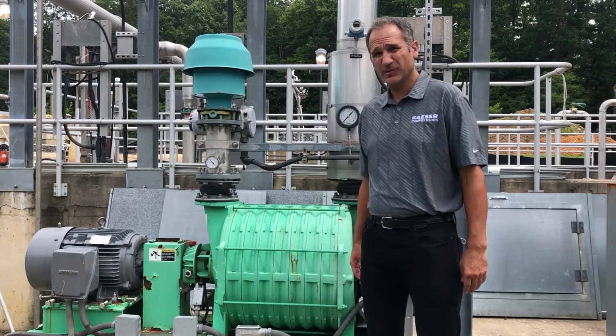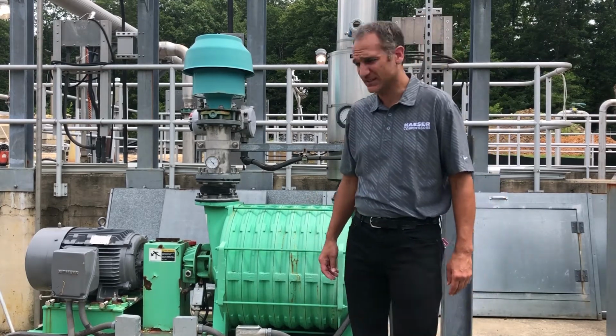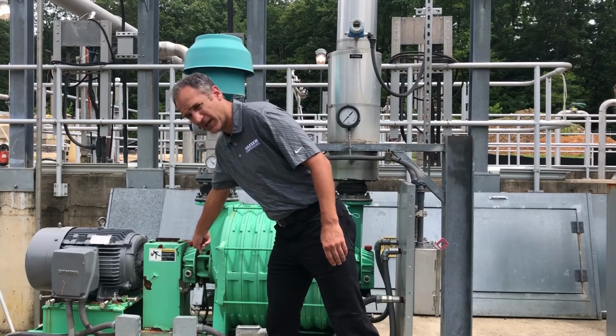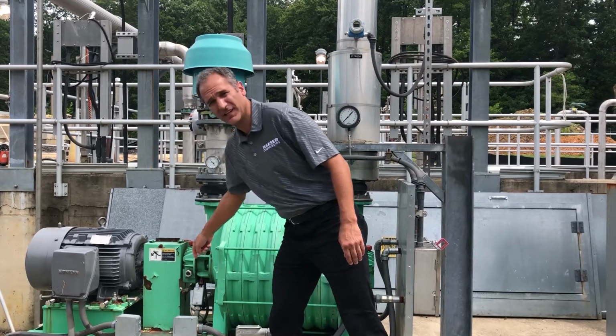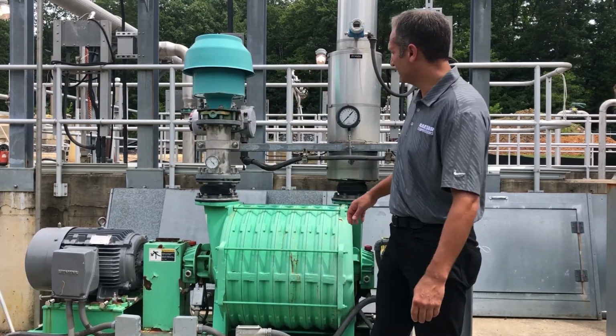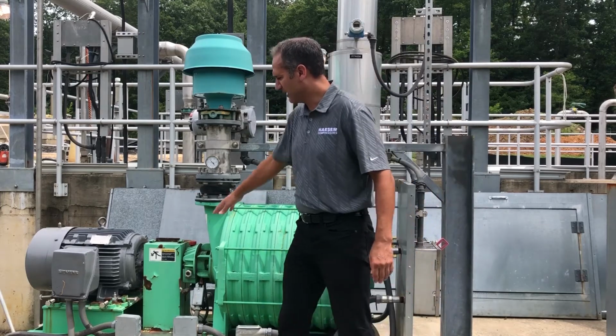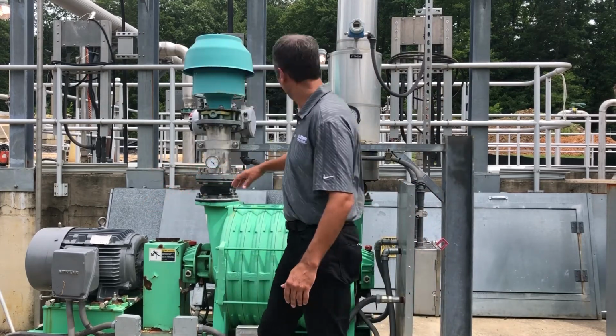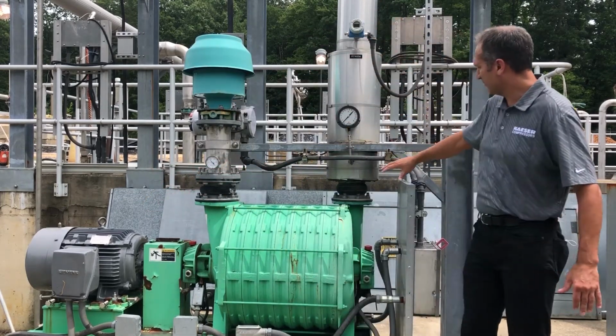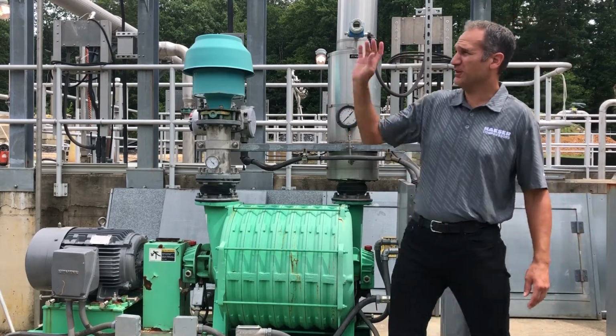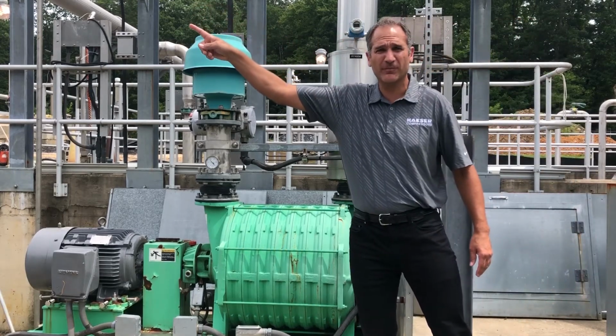The first thing is, whenever we get performance on many blowers, a lot of times they just give us the coupling power. That's the power at the coupling of the blower, and it excludes things such as your inlet filter, coupling losses, drive motor losses, flow losses from the pipeline and back pressure, as well as the controls, which are in another room.